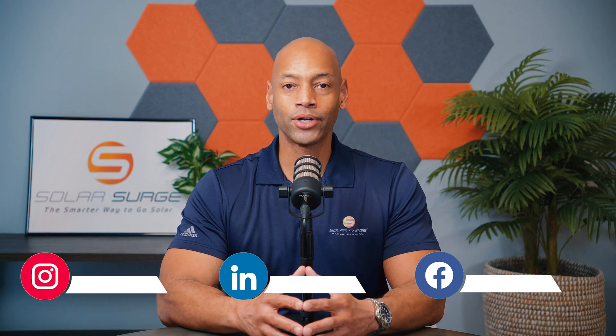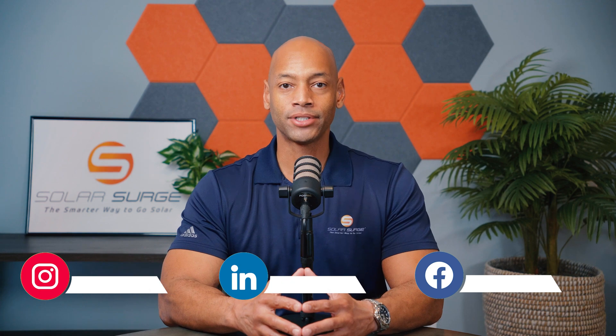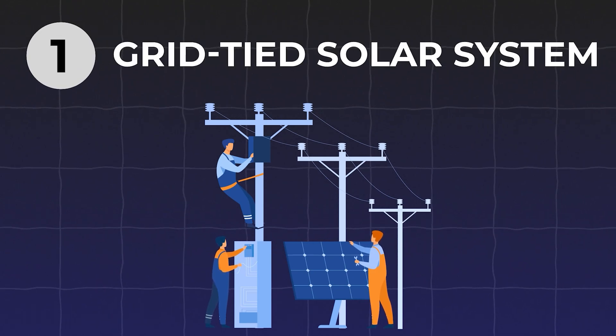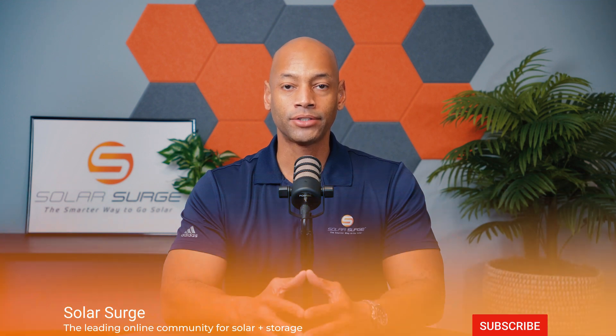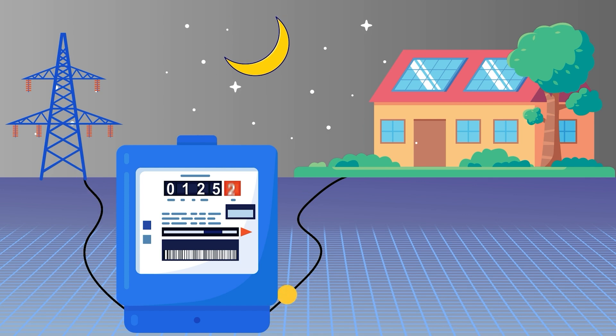The answer is it depends on which type of solar power system you have. The first and most popular is what we call a grid-tied solar power system. With a grid-tied system, your solar system works in parallel with the utility service. During daylight hours when the solar panels are producing, you can be directly consuming the solar energy within your house, and any excess solar energy can be pushed back or sold back to the power company for full price credit. During the evening hours you pull back the energy you need using the credits built up during the daytime.